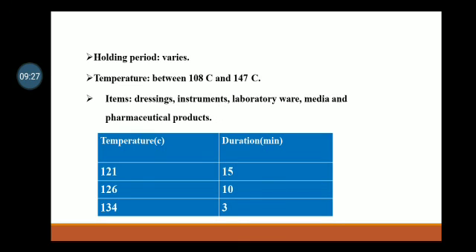Items like dressings, instruments, laboratory ware, media, and pharmaceutical products, they all are sterilized by using an autoclave. Temperature and duration: 121 degrees Celsius for 15 minutes, 126 degrees Celsius for 10 minutes, 134 degrees Celsius for 3 minutes.